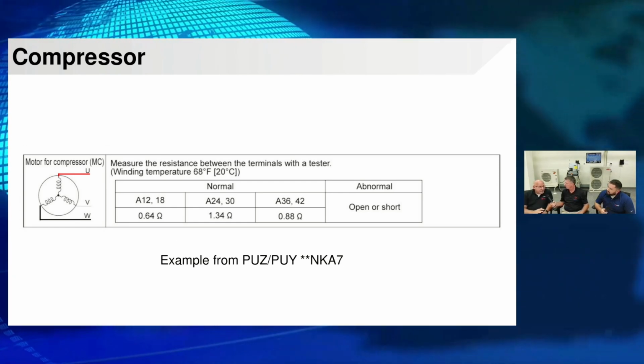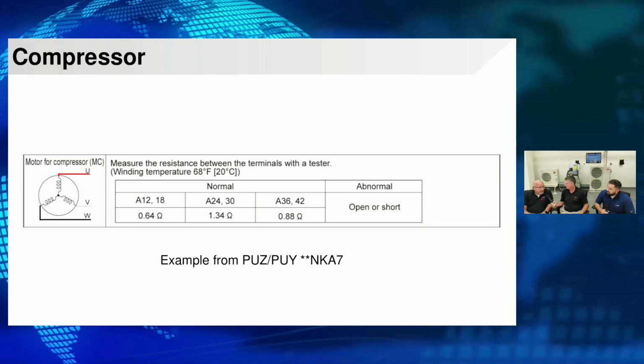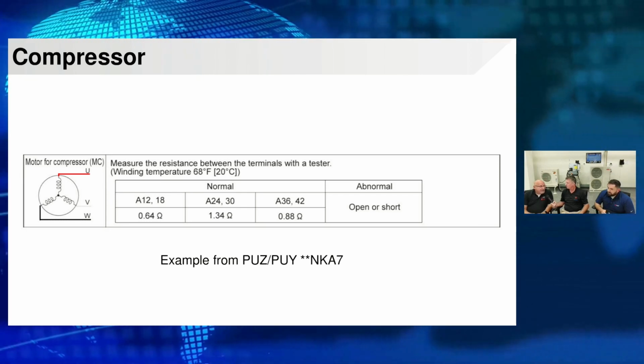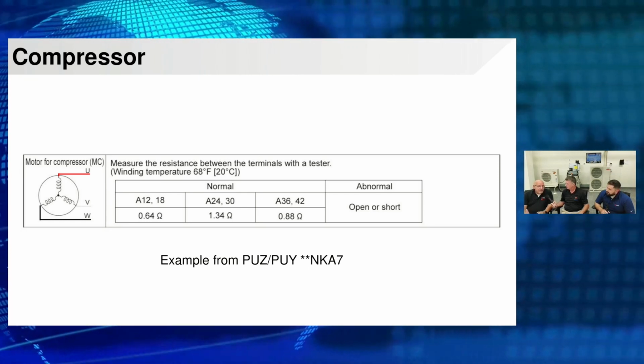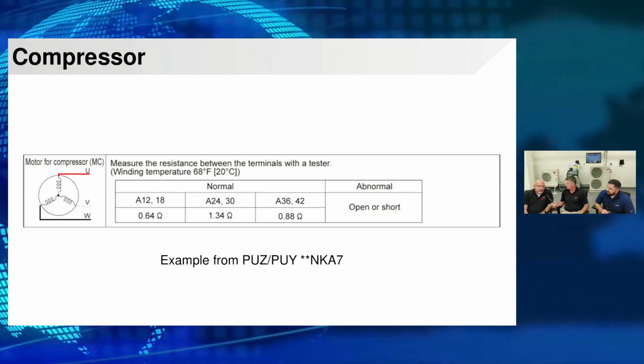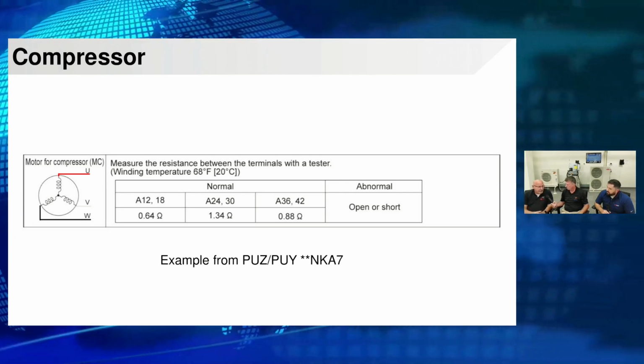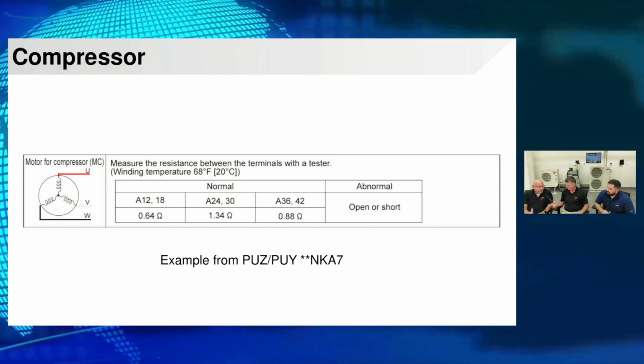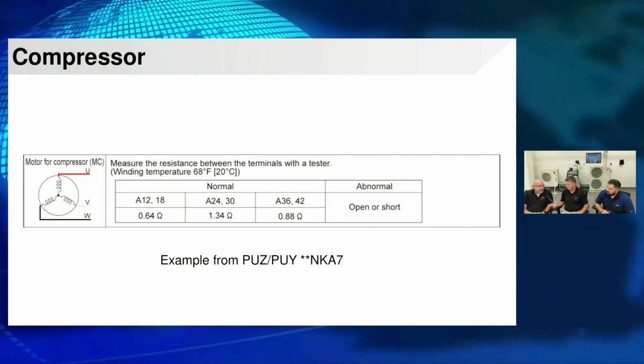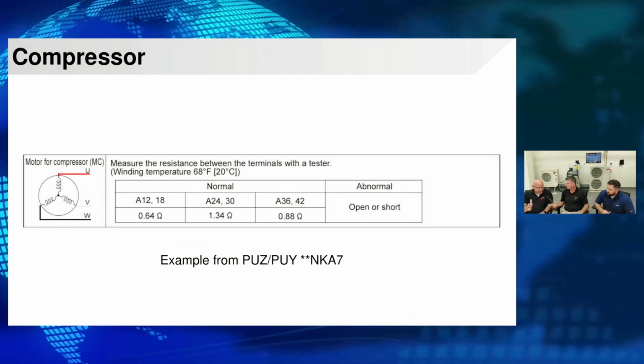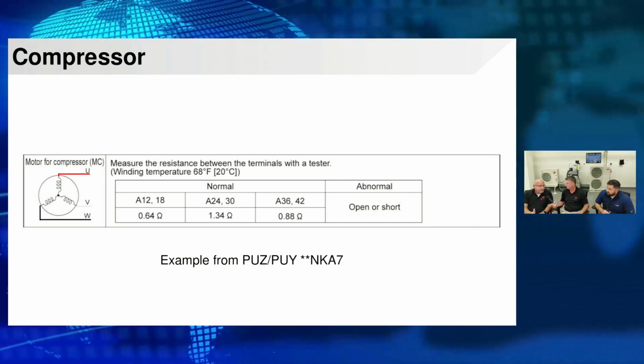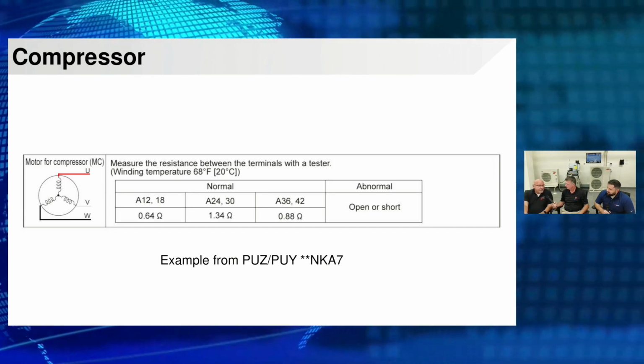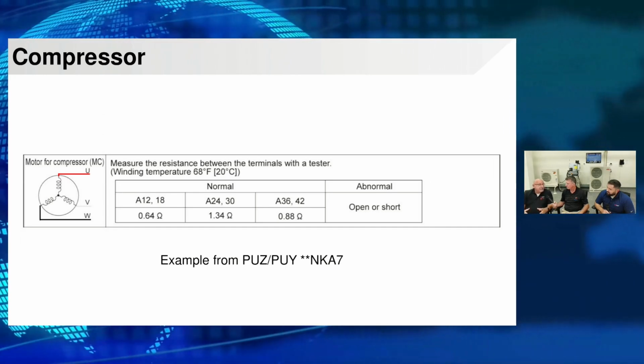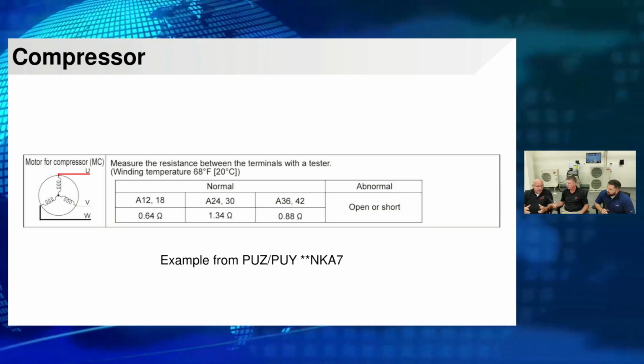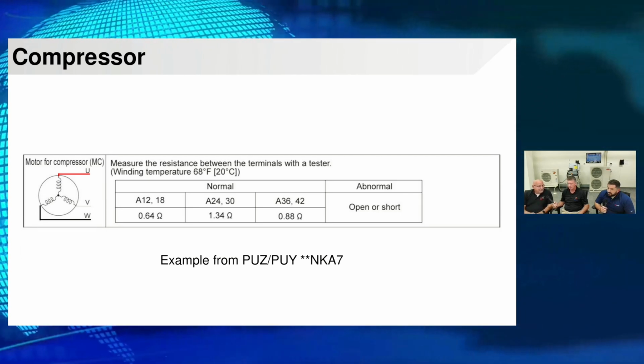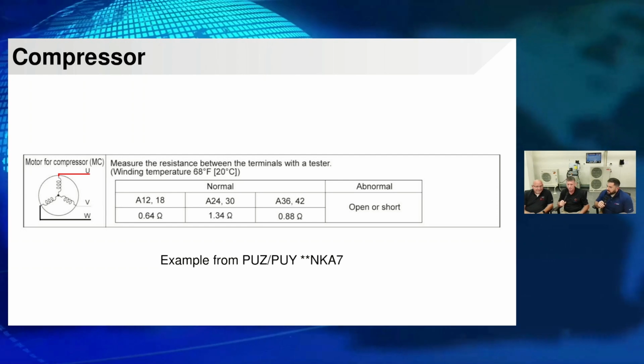And checking mega ohms, you need to be aware that liquid refrigerant is conductive. So mainly on startups, if you're installing an inverter compressor in the winter and you don't power up that outdoor unit for at least 12 hours and you start it up, you will have an immediate dead short, because you're going to power the compressor and you've got a potential crankcase full of liquid refrigerant. It's a potential short right on startup. You'll actually even notice on that particular site, it's telling you the rating at a specific temperature.